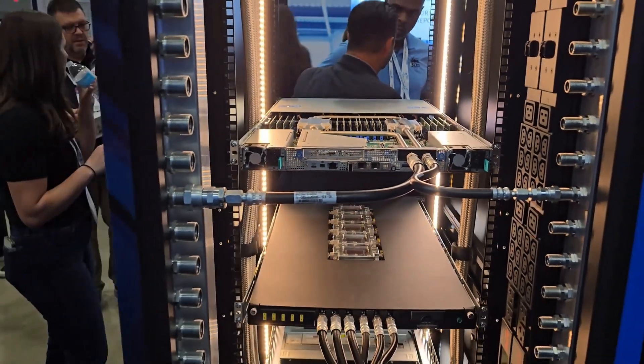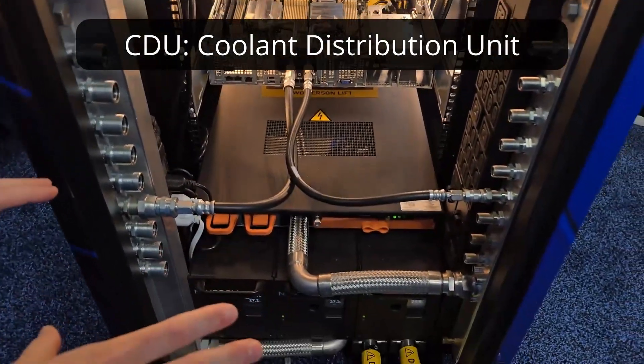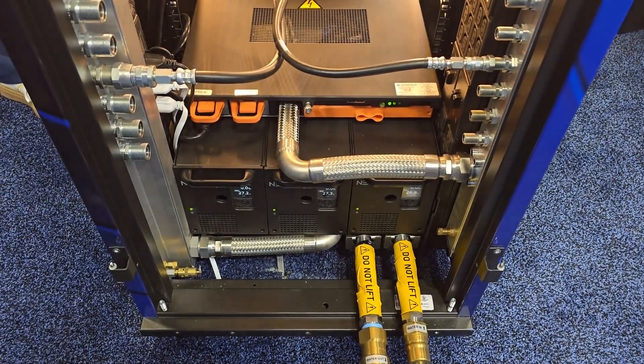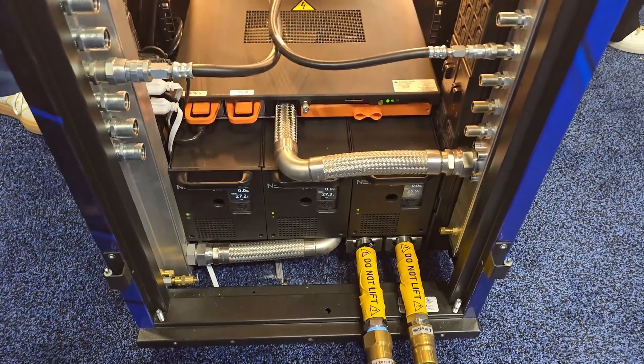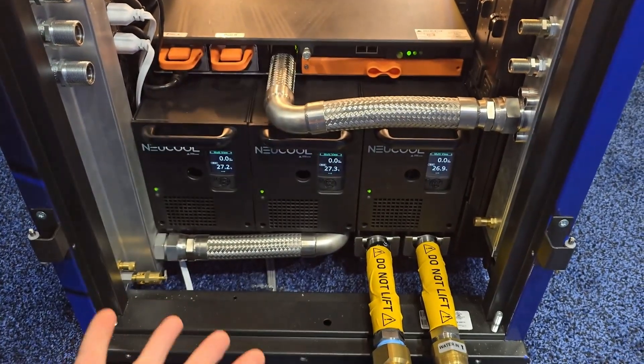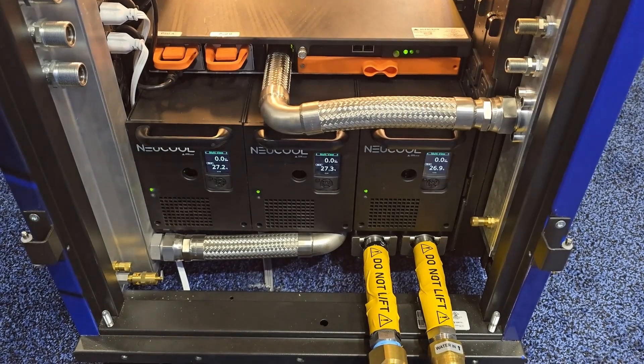What we're looking at here is the back of a two-phase direct-to-chip liquid cooling solution. Again, if it looks like a single-phase water-based solution, it should. We have a CDU at the bottom of the rack that has your pumps and heat exchangers. You have facility water coming to the back of the CDU to ultimately reject the heat. I'll point out that our CDU has nice features for serviceability — I can easily remove any one of these three pumps, and the other two pumps will increase their flow rate so that the pump is completely hot-swappable with no loss of cooling during that operation.